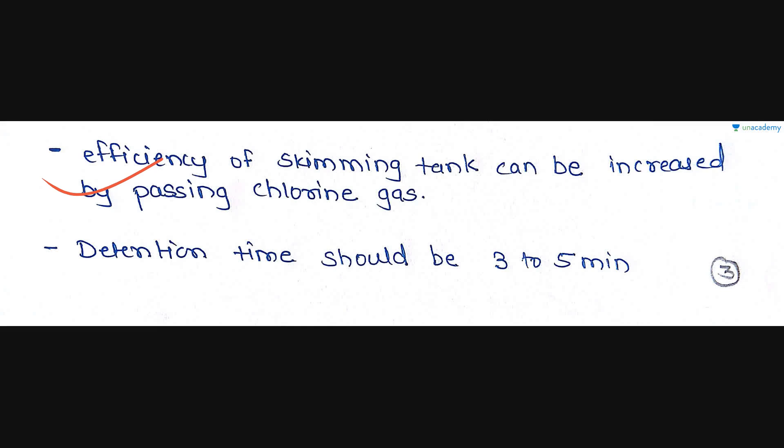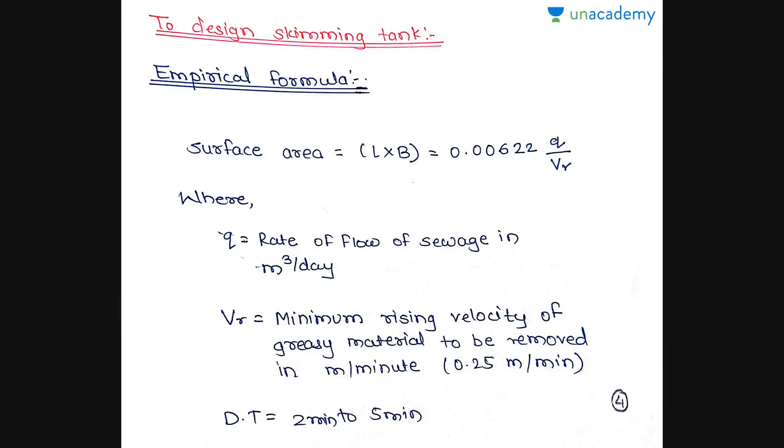Adding chlorine increases the efficiency of the Skimming Tank by 3 to 4 times, making it very effective. The detention time should be 2 minutes to 5 minutes.